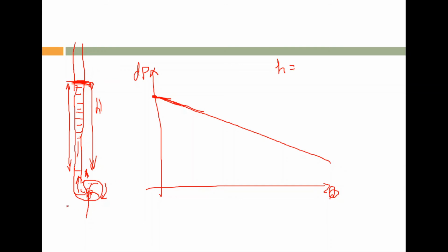So theoretically, what you can see is that the discharge pressure, or simply head H, is equal to the power dissipated by this pump divided by rho g and Q. Here efficiency is also an important factor. So you can see that if you are decreasing this head, definitely the flow rate will increase. Okay, practically what we would expect is a linear decrease in discharge pressure with respect to the increase of flow rate.